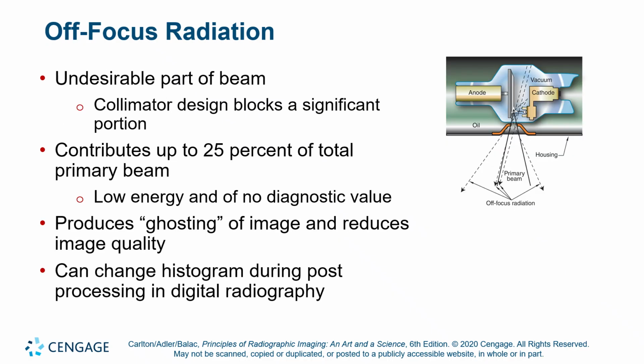Okay. Off-focus radiation. So the intent is for that electron stream to remain kind of like a rifle shot, where it's pointing only at one specific spot on the anode target, and all the electrons theoretically are supposed to bombard inside this little tiny target region. Okay? But that's not what happens. What happens is electrons are quantum objects, and so although we like to think of them as particles, they occasionally, according to probability, do screwy things. One of the screwy things they do is they don't take the shortest path, they go to the entire anode wheel. They go to the tube housing. Okay? They go basically everywhere except for staying at the filament. Okay?